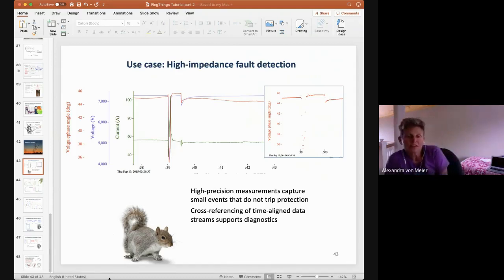These were just some illustrations of stuff we can measure with micro-PMUs in the real world. And voltage phase angle will swing with a disturbance, just like voltage magnitude. So this particular incident did not end well for the squirrel, but it was a great moment for micro-PMU diagnostics.